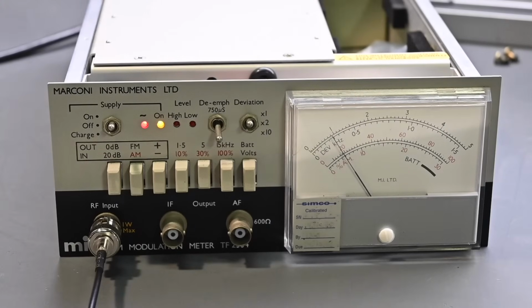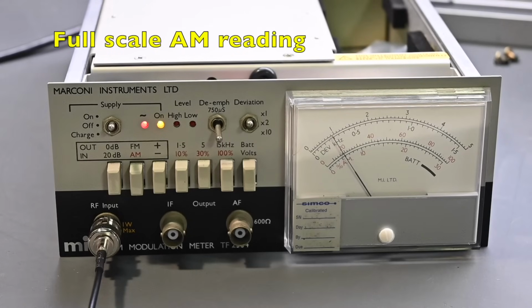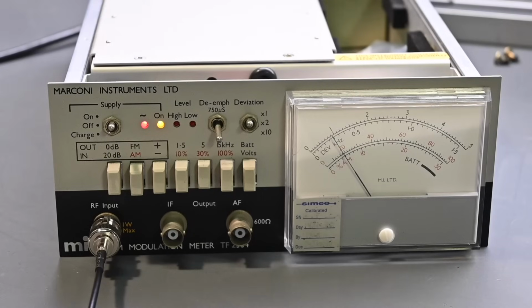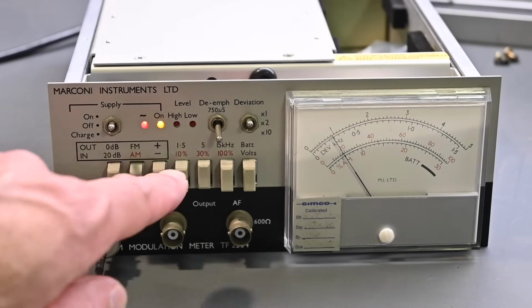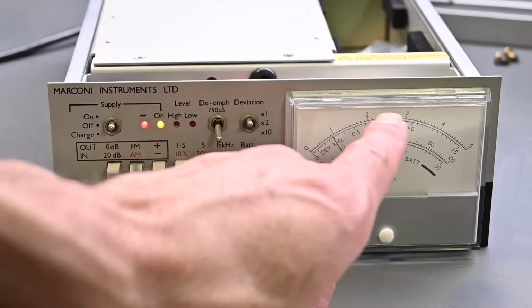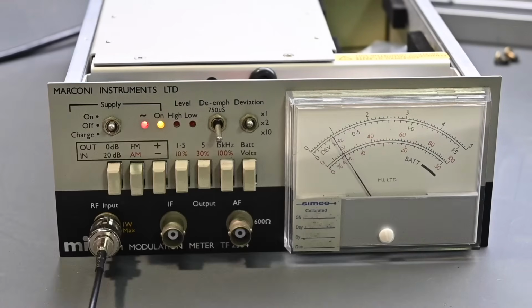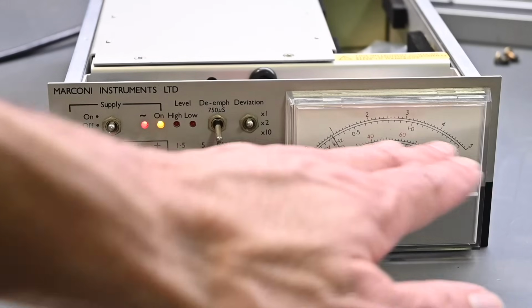So I went back and took a second look at the calibration on the middle range, so the 0 to 5 kilohertz, just to make sure it was as accurate as I could possibly make it without getting into other calibrations in the instrument, just this one adjustment, just making sure it was dialed in as closely as possible. And I tried to dial in the AM modulation readings a little bit closer, but when I did that, the FM modulation readings are just too far off. So I went back and recalibrated on the FM modulation right at mid-scale instead of the extreme range. And I'm happy with the result. I think it's really more of just a linearity issue at this point on this meter movement.